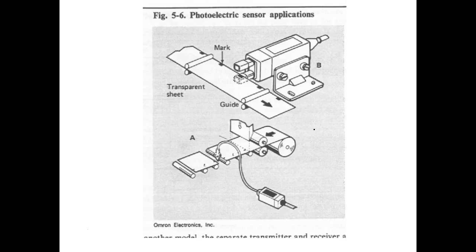So photoelectric sensors, this is not your book, this is out of another book. We use these all over the place. The only thing you've got to worry about is the cleanliness. One of the guys says that's part of their preventive maintenance. They go out with a rag and clean these things off. It's just like the inside of the windshield in your car, which is not exposed to the dirt, but it still gets stuff on it. You have to come in there every once in a while and clean it. So all these usually will need someone to come in and clean them every once in a while.